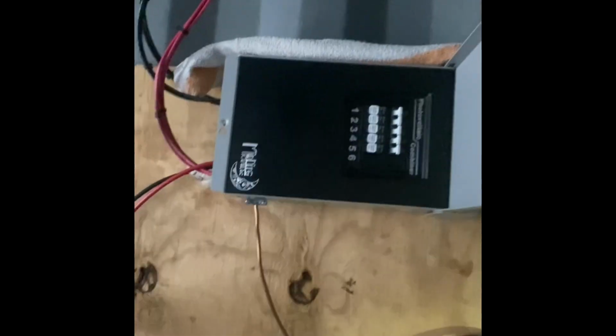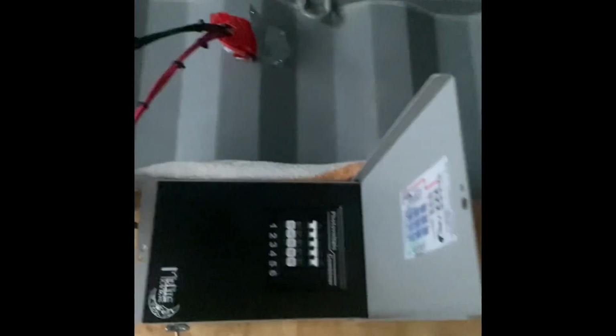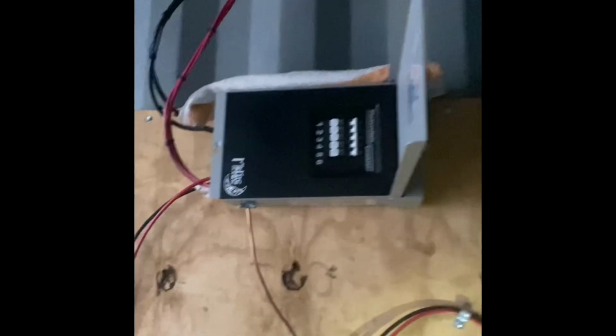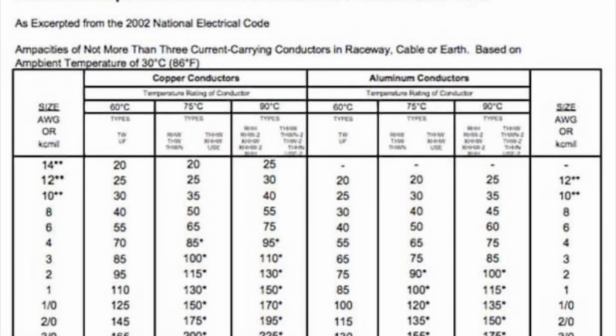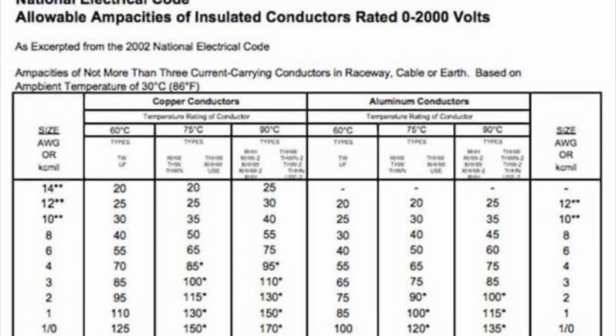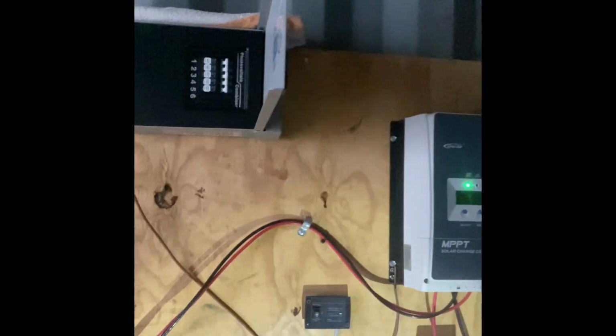I have 10 gauge coming in, 6 gauge coming out. The 10 AWG wire, or 10 gauge, I believe handles around 30 amps, and that's given according to your NEC chart, your National Electric Code. Be sure to check that while you're designing your system, so that you can make sure you give yourself an adequate wire thickness to carry the amps. Always go over.